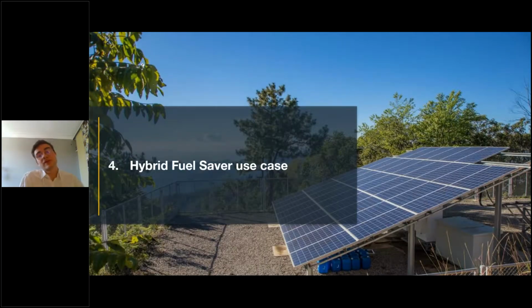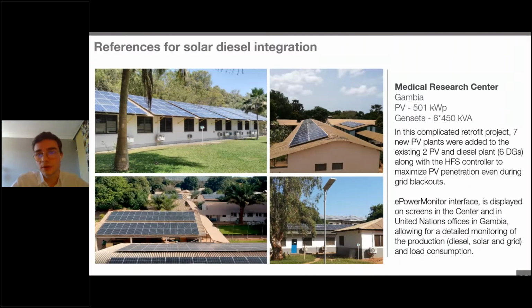Now let's move on to the hybrid fuel saver, one of our important references, a medical research center in Gambia. Here we have 500 kilowatt peak of PV with different subsites on the PV end, many inverters, and 6 different gensets to manage. On this site, commissioned last summer, we installed our hybrid fuel saver controller, which manages feed-in when the site is grid-tied, as well as genset minimum loading management during off-grid times and blackouts.